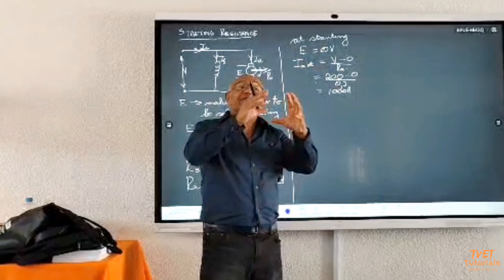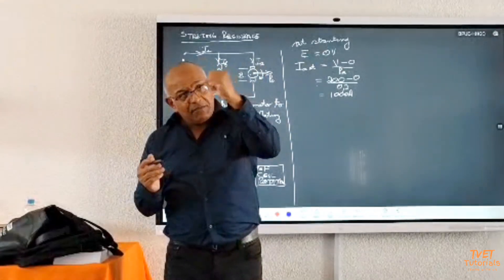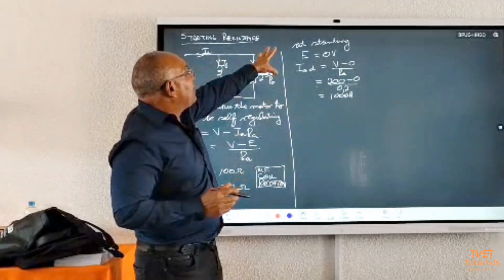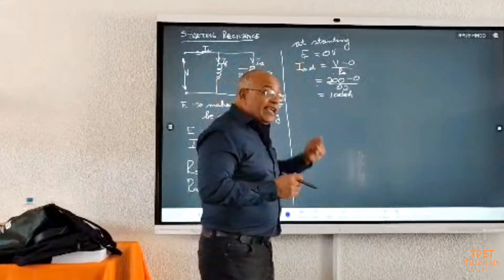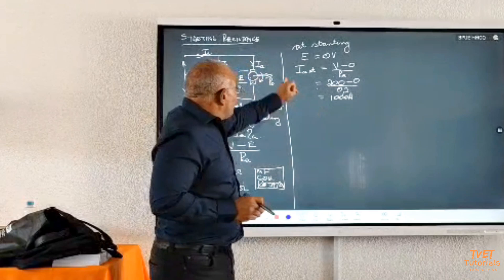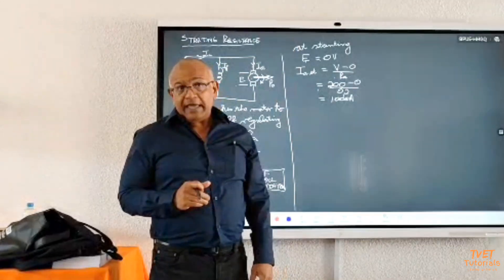But because the rotor is beginning to rotate, can you see the EMF is beginning to develop? As you exclude each resistance element, each time you move the arm, you exclude resistance from the armature, you will find automatically the EMF begins to grow. When we say it is self-regulated, it helps to limit the high starting current. That's the function.